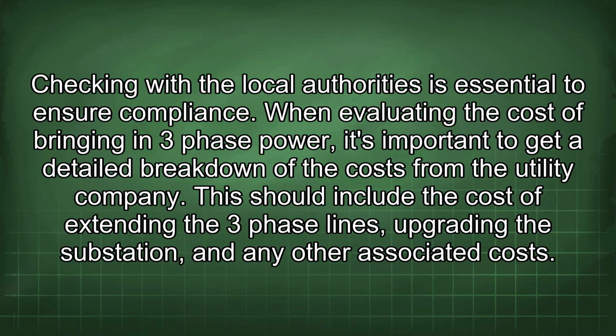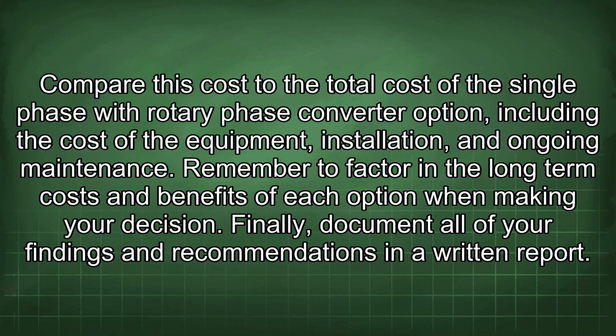When evaluating the cost of bringing in three-phase power, it's important to get a detailed breakdown of the costs from the utility company. This should include the cost of extending the three-phase lines, upgrading the substation, and any other associated costs. Compare this cost to the total cost of the single-phase with rotary phase converter option, including the cost of the equipment, installation, and ongoing maintenance. Remember to factor in the long-term costs and benefits of each option when making your decision.